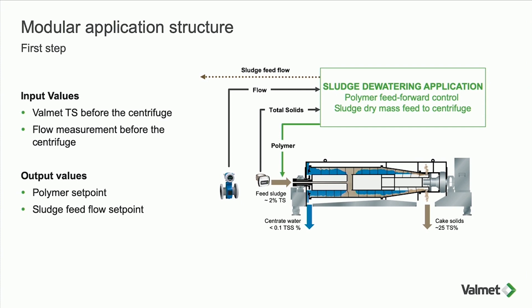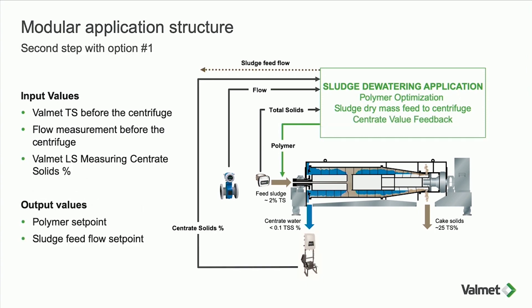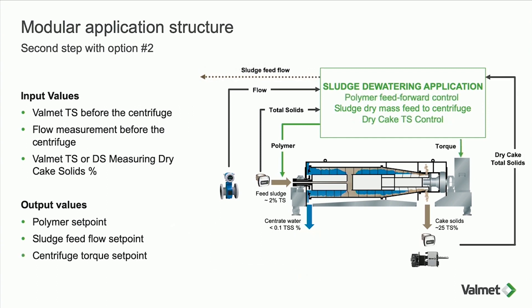The next step could be adding Valmet LS, so we're measuring centrate as well. In addition to controlling mass flow, we use the actual centrate value to give feedback for the polymer control — we can see what the polymer is doing to the centrate, and this is all handled automatically. Alternatively, if we have a dry cake measurement instead, we can also manipulate the torque value automatically to optimize the dry cake at the end of the centrifuge.